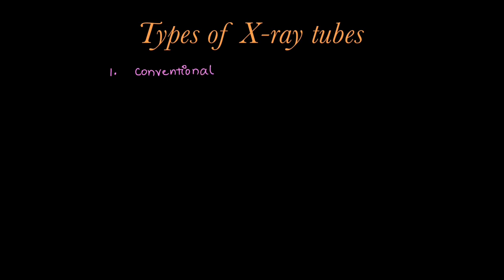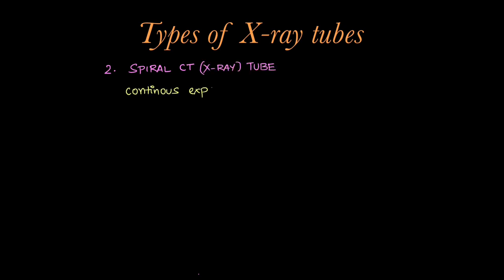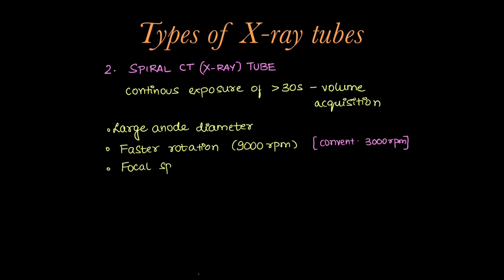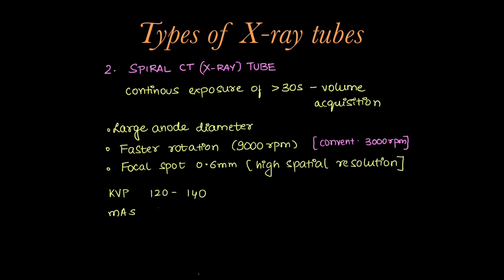Coming to the most important part: types of x-ray tube. We already learnt how the conventional x-ray tube works. Now we will learn about the spiral CT x-ray tube, used in CT for continuous exposure for more than 30 seconds for volume acquisitions. Hence, a large anode diameter is used. There is faster rotation speed of 9000 rpm, compared to 3000 rpm in normal tubes. The focal spot is smaller at 0.6 mm for higher spatial resolution. KVP 120 to 140 is used, with MAS up to 400.